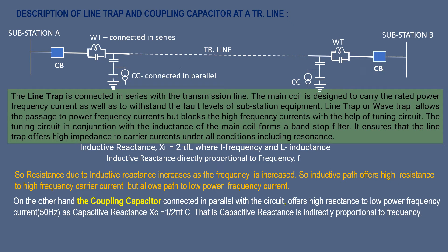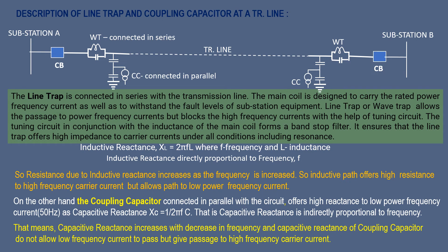On the other hand, the coupling capacitor connected in parallel with the circuit offers high reactance to low power frequency current (50 Hz), as capacitive reactance XC = 1/(2πfC), meaning capacitive reactance is inversely proportional to frequency. That means capacitive reactance increases with decrease in frequency. Therefore, the coupling capacitor does not allow low frequency current to pass but gives passage to high frequency carrier current. Separation between the two currents is achieved through this process.